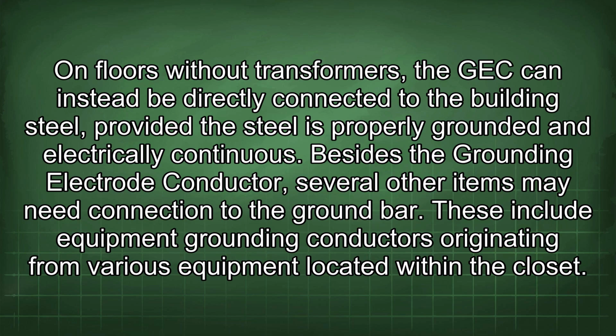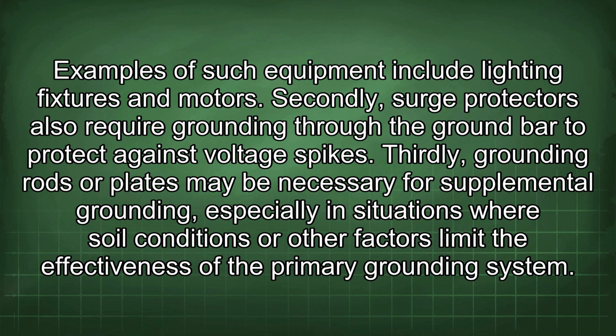Besides the grounding electrode conductor, several other items may need connection to the ground bar. These include equipment grounding conductors originating from various equipment located within the closet. Examples of such equipment include lighting fixtures and motors. Secondly, surge protectors also require grounding through the ground bar to protect against voltage spikes. Thirdly, grounding rods or plates may be necessary for supplemental grounding, especially in situations where soil conditions or other factors limit the effectiveness of the primary grounding system.